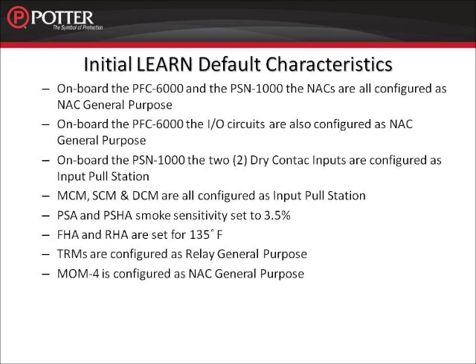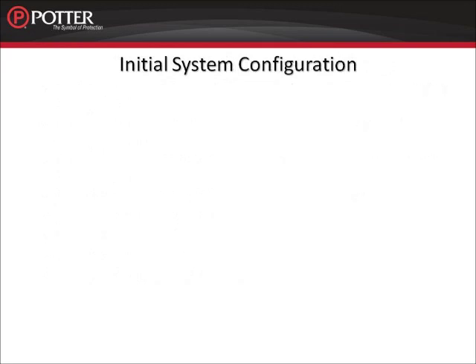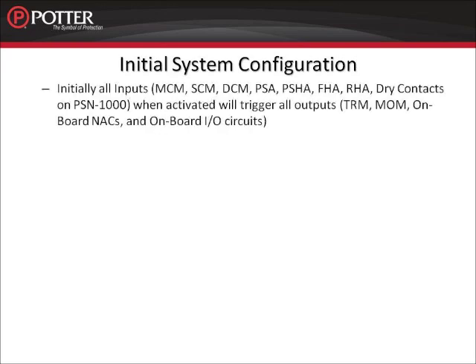These are the default initial characteristics when running a LEARN from the panel. These characteristics can be altered using the upload and download software. Now that we know the initial device characteristics, we can talk about the default system configuration after running a LEARN. Initially, all inputs — the MCM, SCM, DCM, PSA, PSHA, FHA, RHA, and the dry contact inputs on the PSN 1000 — when activated will trigger all outputs: the TRM, the MOM4, the onboard NAC, and the onboard I-O circuits. All of these devices are initially assigned to zone 1.